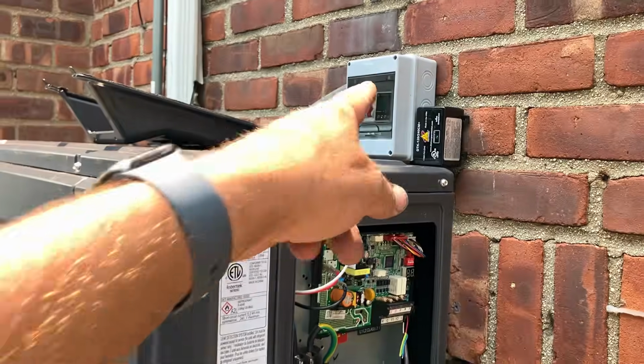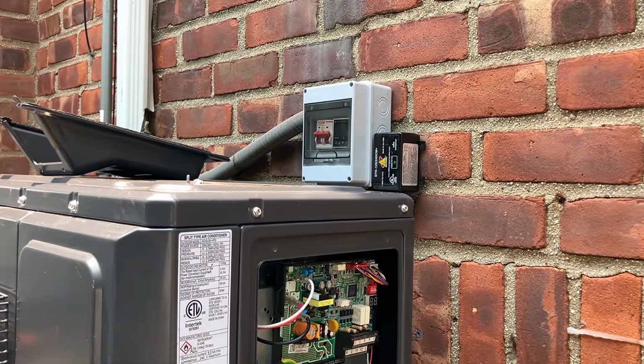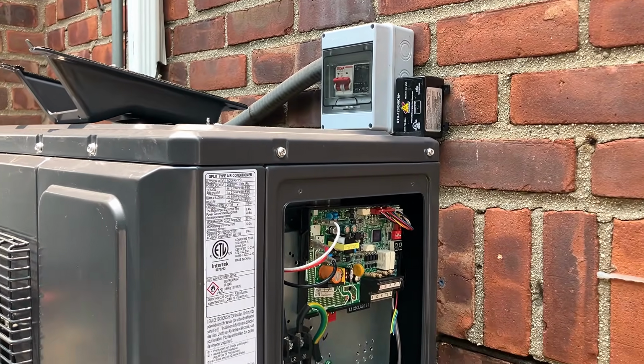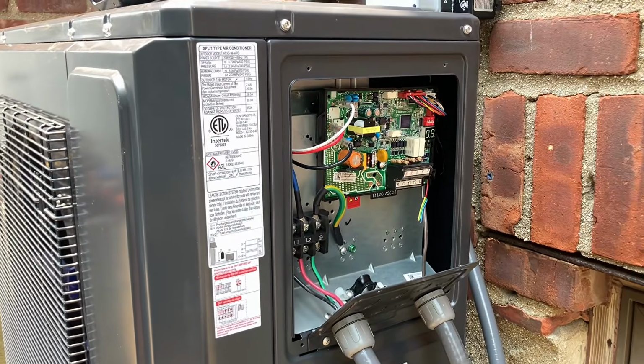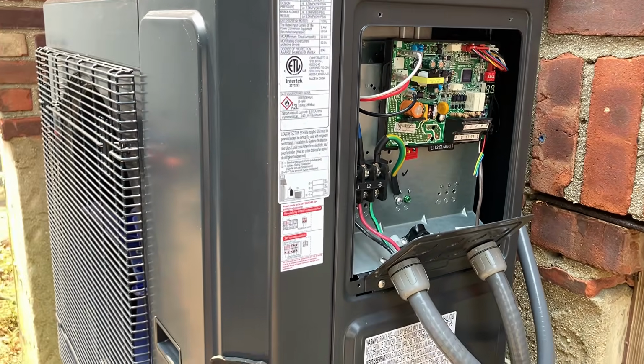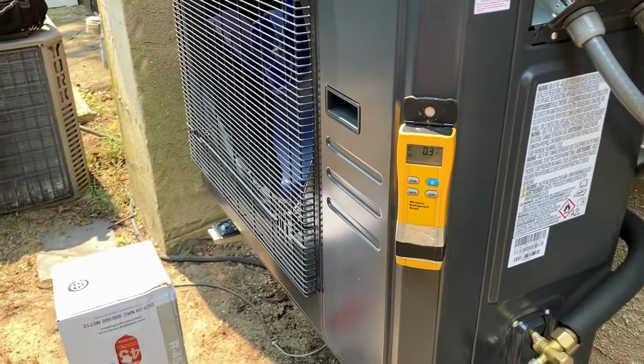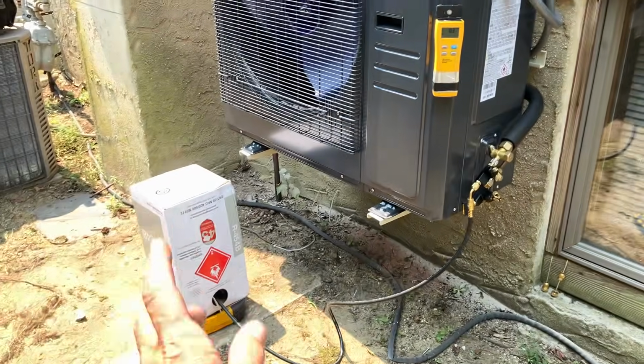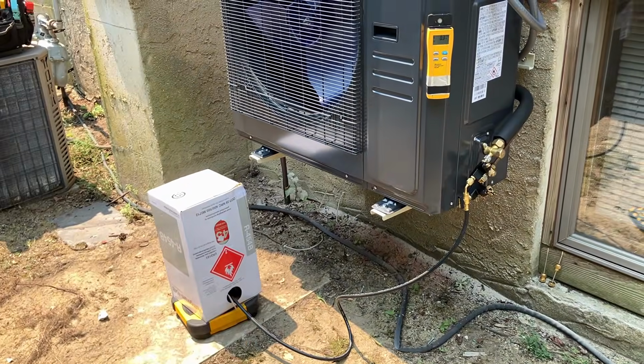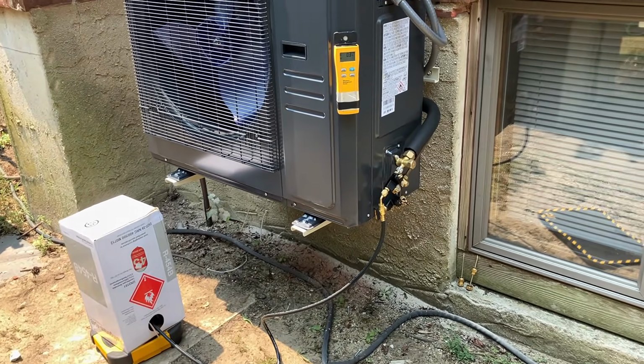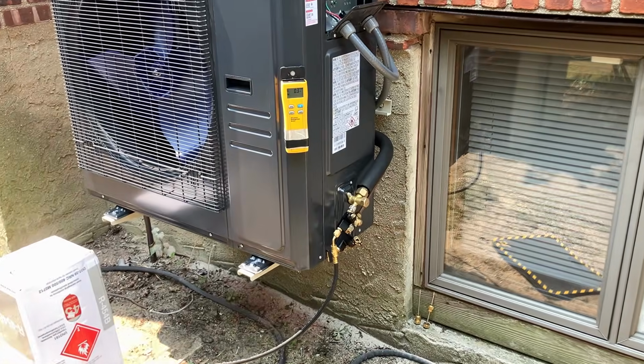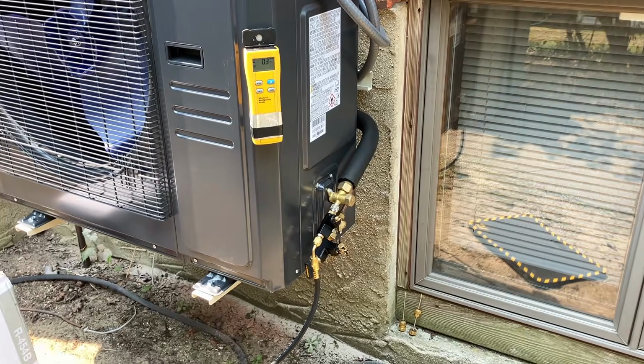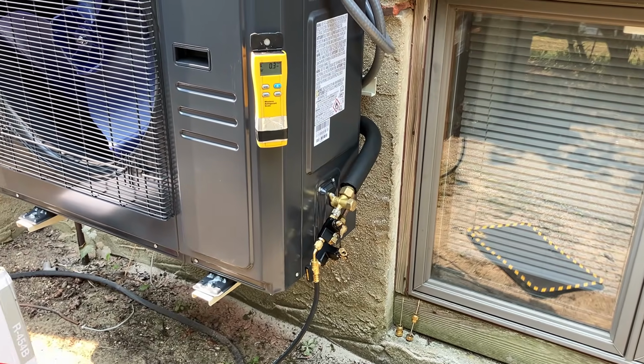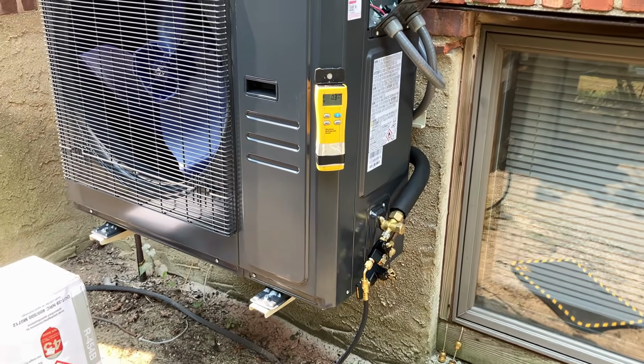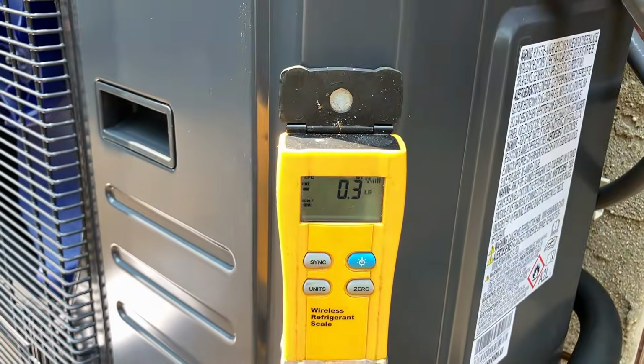In a few seconds, our power management device will send power to the load side of the system that is illuminated. We have an active call for cooling, and once this system turns on, we're going to add 1 pound of refrigerant to the system. So I'm weighing in as a liquid R454B. I've got my charging hose connected to my suction side, the line with the large valve on it, 3/4 inch line. And we're going to add 1 pound. So right now we're at 0.3.